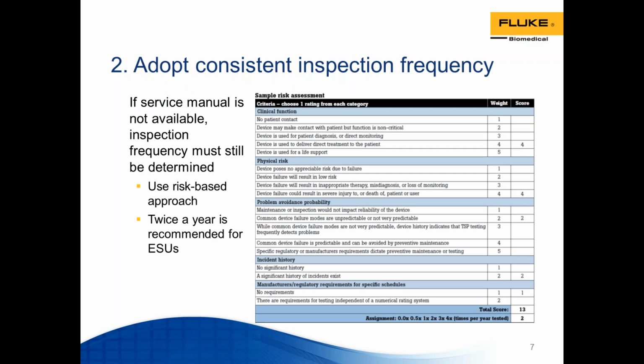Follow the recommended inspection frequency, and there are ways you can cross-check on that frequency if you wish. Adopt a consistent inspection frequency. If the service manual and inspection procedure is not available, you're still responsible for coming up with an inspection frequency. That's what you will be audited to. So to determine that, you might use something like this, what you see here, a risk-based approach.